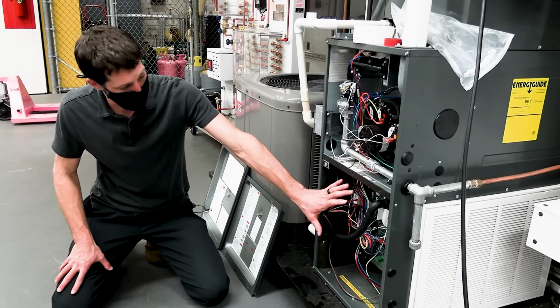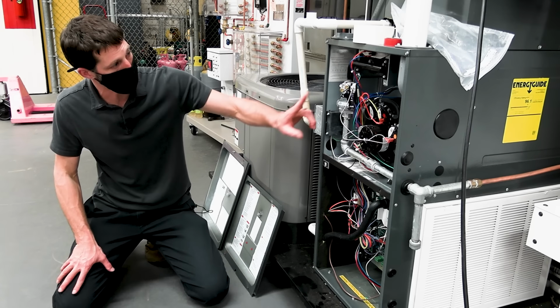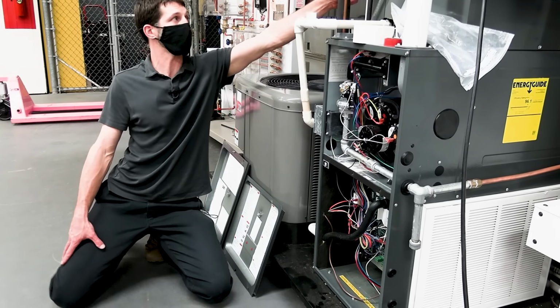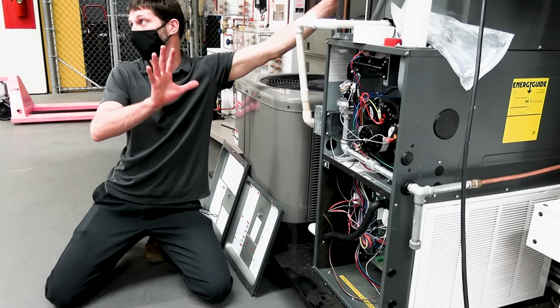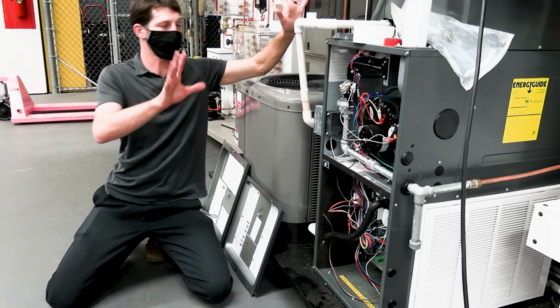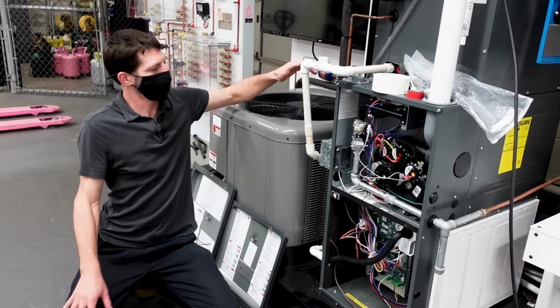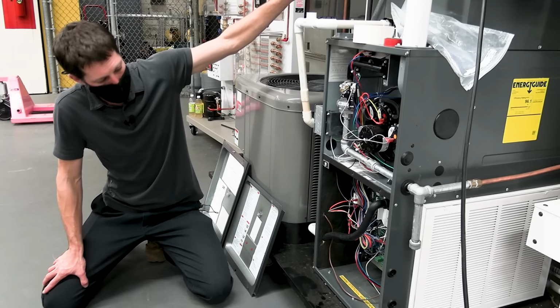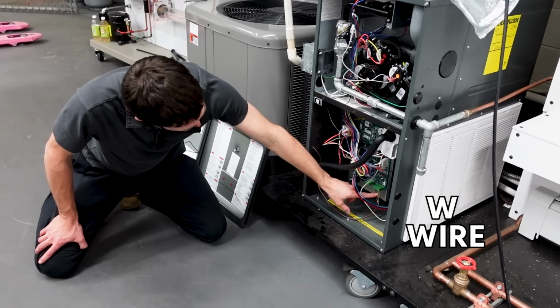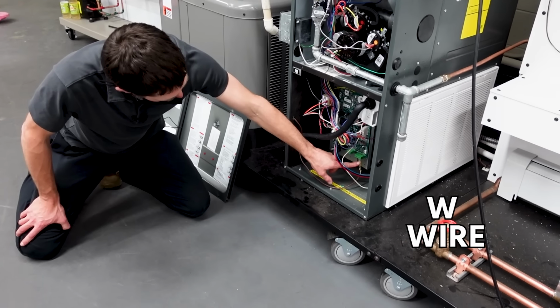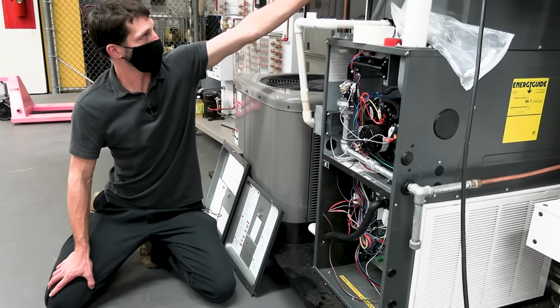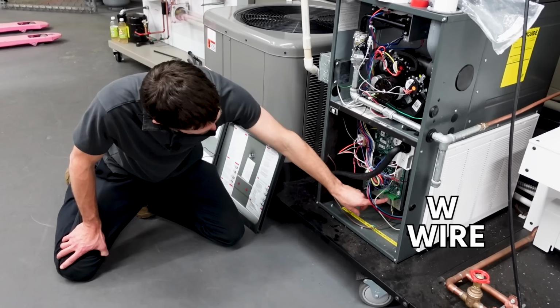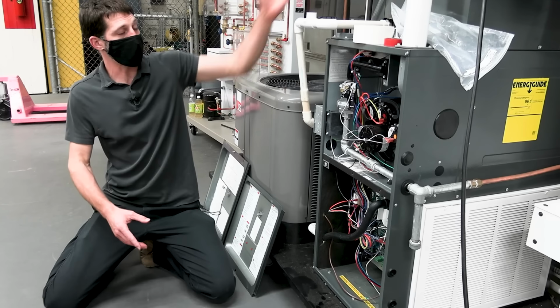The control board is a smart thing right here. So even though this is 2-speed, we wouldn't have 2 speeds at the thermostat up here if it's a basic thermostat. I'm not talking about the communicating ones and all that, and they're not even called thermostats, they're interfaces and things. But anyway, so down here you just have one W wire, and that's your heat wire. So as soon as you're sending a signal from the thermostat to the letter terminal W, you've got to remember that your thermostat acts as a switch.